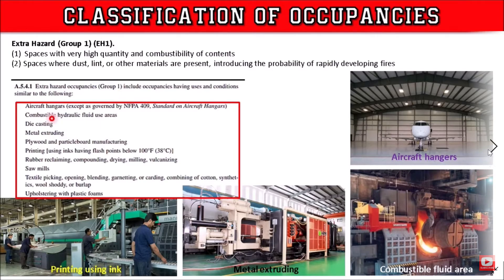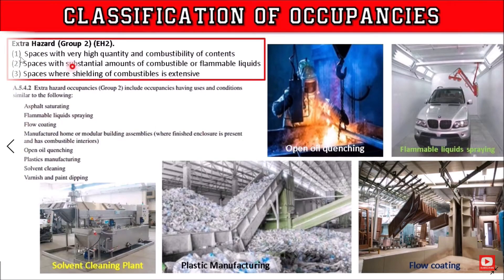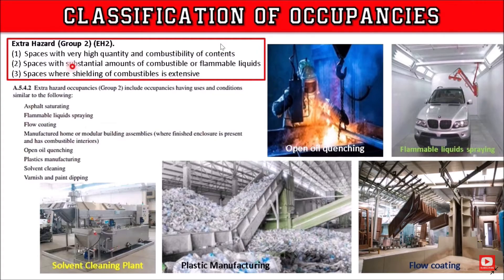To summarize: light hazard, ordinary hazard group 1, ordinary hazard group 2, extra hazard group 1, extra hazard group 2. Extra hazard group 2 is a space with very high quantity and combustibility of content, a substantial amount of combustible or flammable liquids, and where shielding of combustibles is extensive, raising the heat release rate significantly.